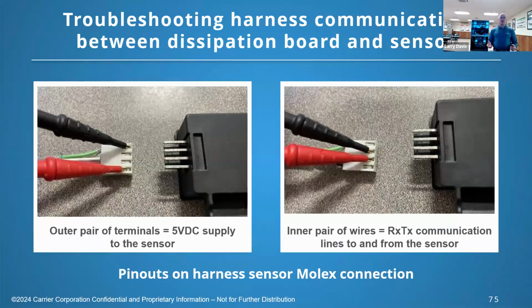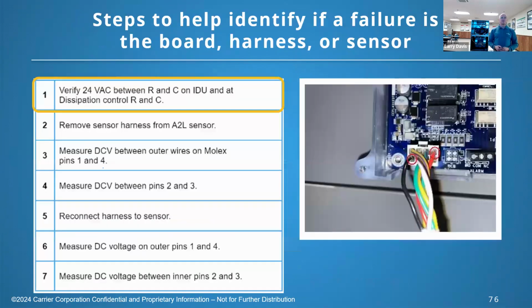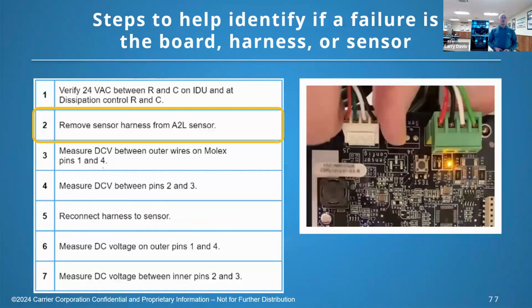So checking the voltage from your board. There are 4 pins going to that sensor. The outer 2 are a constant 5-volt DC power supply to the sensor, and the inner 2 terminals are the communication between the sensor and the board. So the board provides 5 volts DC to the sensor on the outer pins, and then the sensor communicates with the board on the 2 inner pins. So checking that, make sure you have power on your board. Do we have 24 volts on our board? Is our light on? Remove the sensor.